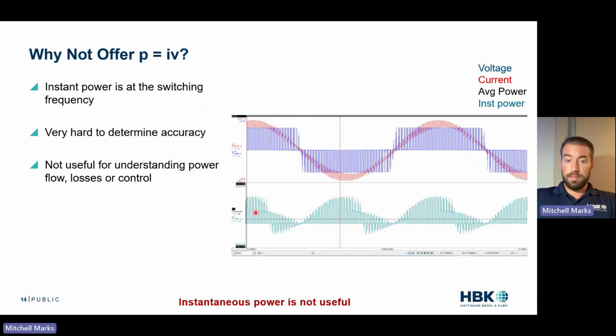And then we have our calculated power in green. And we can see we have negative power swings. We have power at the switching rate because we're multiplying point by point. So instantaneous power is at the switching frequency. This is why we can't just take V times I. It's useless. We need the correct averaging period, especially to get an accurate result. It's very hard to determine the accuracy on this instantaneous because it's negative, it's positive. When the average is 32, you're getting 150 and negative 32, and it's just outrageous. So it's really not useful for understanding the power flow losses or controls.